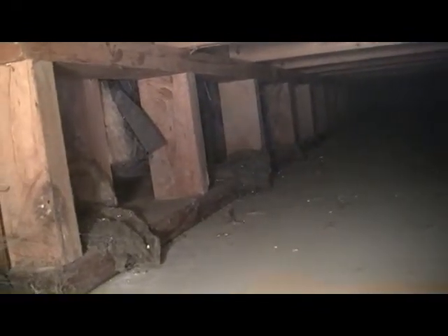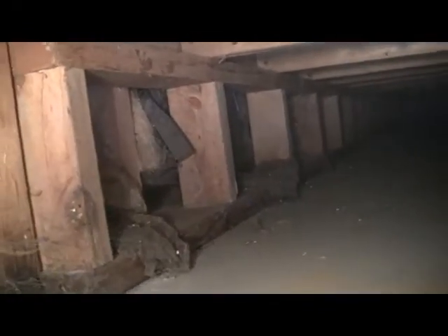We've come back into the actual area where the furnace is. We've opened up the fan housing of the furnace and we're looking down below it back into the area that exists underneath the stage. You can see that back on the north wall, which is to the left there, the studs of the exterior wall are exposed and open. The insulation that's been in there has fallen out. It's actually allowing air to be pulled down that exterior wall into the furnace as well.